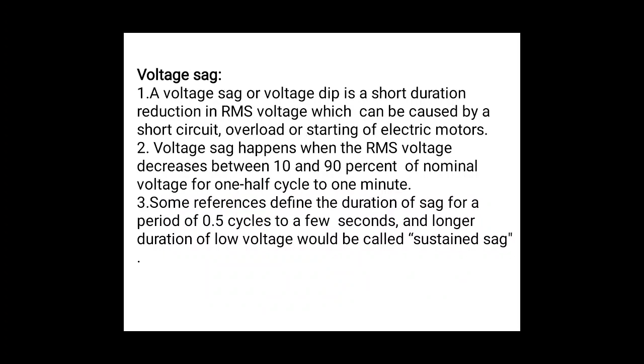Here are several factors given because of which voltage sags happen. Let's read one by one. Since the electrical motor draws more current when starting, as I said, at the time of starting the motor requires more torque, and for the creation of torque it draws a heavy current from the supply system, and as we know that power is constant, then for maintaining that, current rises and voltage drops from its nominal value. That is given here in the first point.